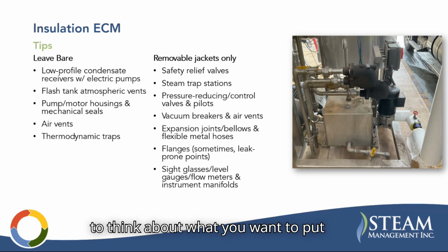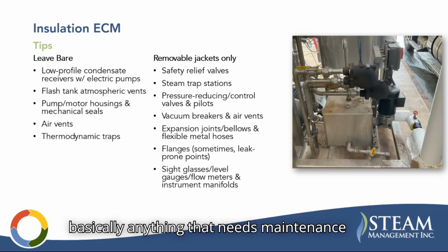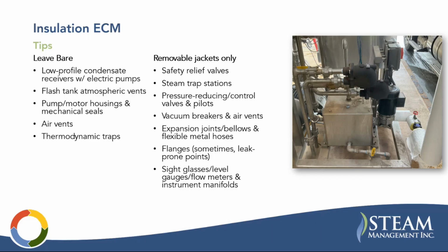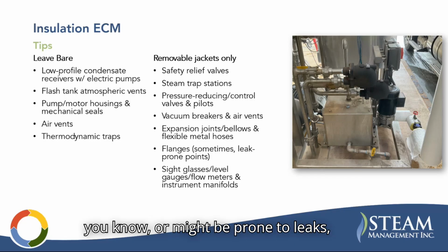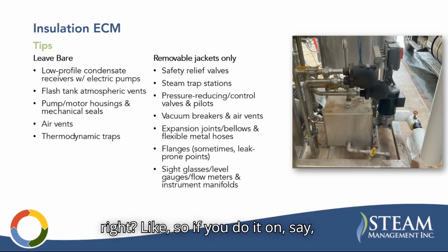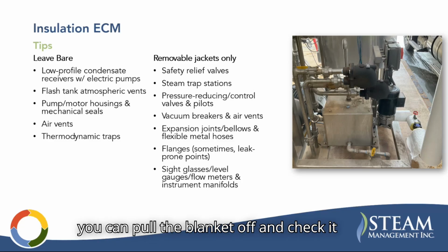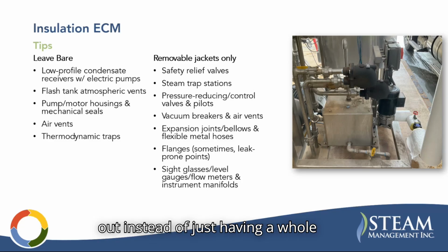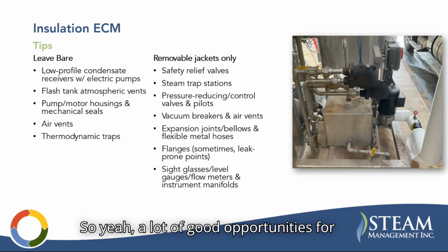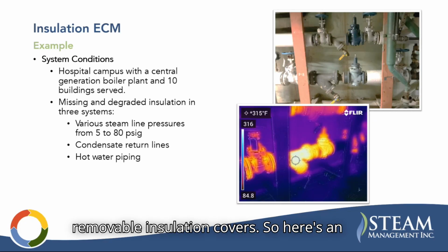And then you want to think about what you want to put removable jackets on. That's basically anything that needs maintenance or testing, or might be prone to leaks, right? So if you do it on, say, a flange set and it leaks, then you can pull the blanket off and check it out, instead of having a whole section of permanent insulation saturated with liquid and ruined. So yeah, a lot of good opportunities for removable insulation covers.